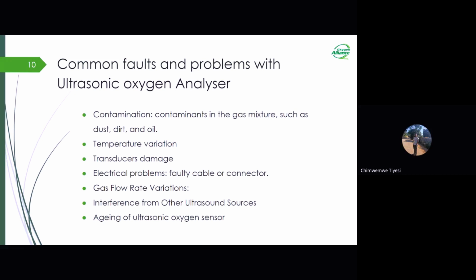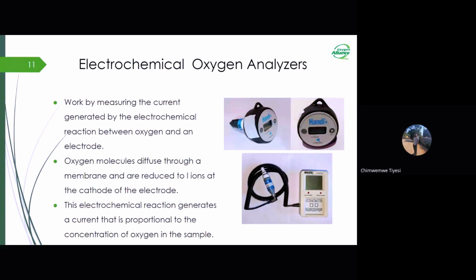Moving on, I will now talk about electrochemical oxygen analyzers. You can see in the graphics, there are two types of electrochemical oxygen analyzers. One is white, the other one is black, white, and blue, made by different manufacturers. These electrochemical oxygen analyzers work by measuring current generated by an electrochemical reaction between oxygen and an electrode. Oxygen molecules diffuse through a membrane and are reduced to ions at the cathode. So the oxygen molecules react at the cathode and produce an electrochemical reaction which generates a current. This current is directly proportional to the concentration of the oxygen.